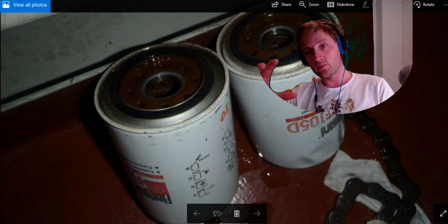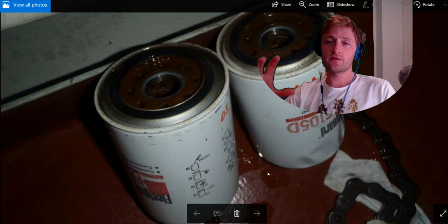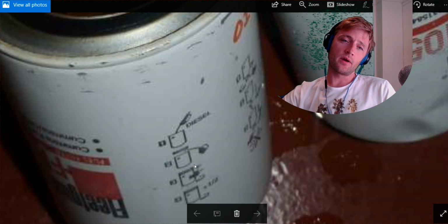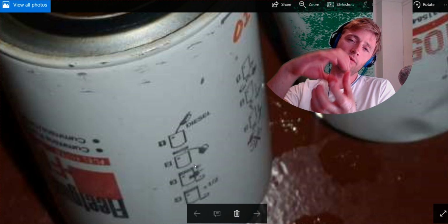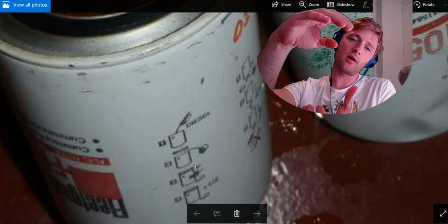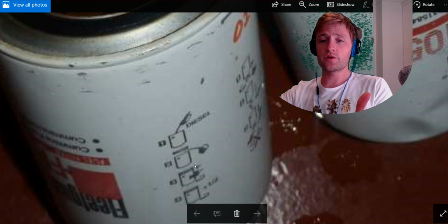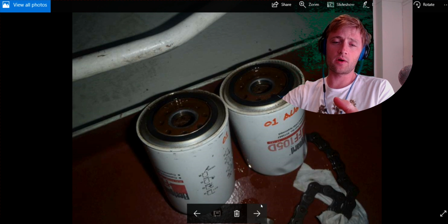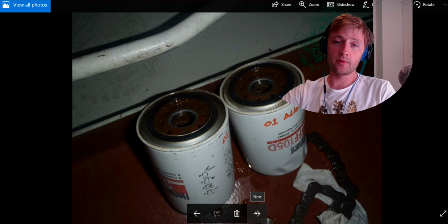Also very important when you do such a job on the emergency generator: after these checks you want your engine to be ready. As you can see here, this is the filter, and when you take it out some air comes in. Just fill your filters, all the filters which you take out, fill them up, also the oil filter and the diesel filter, so your engine can start. In this maintenance, when we finish with all our filters, when we start the engine and we do like that, our engine starts immediately without any problem.